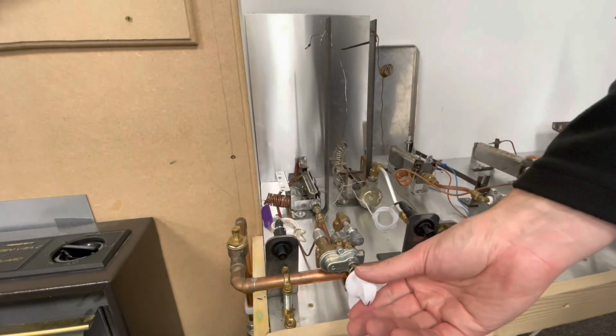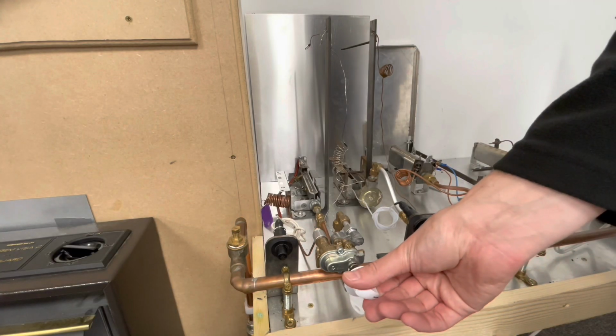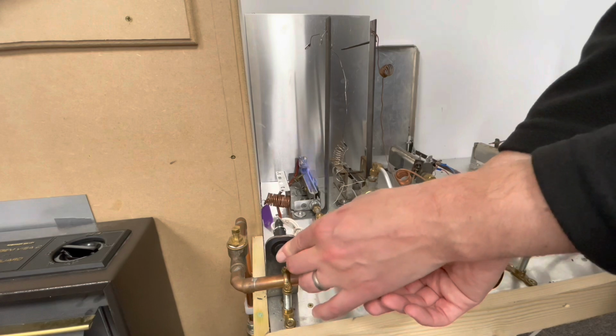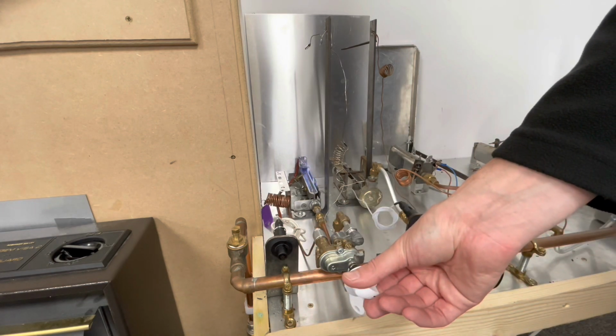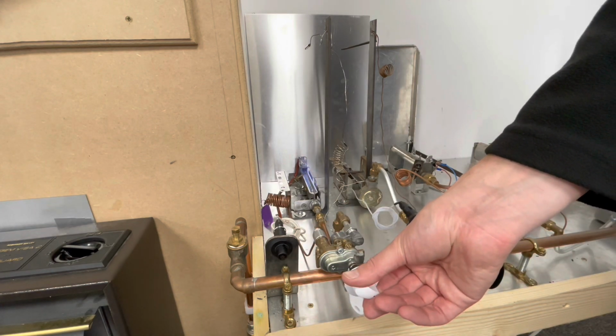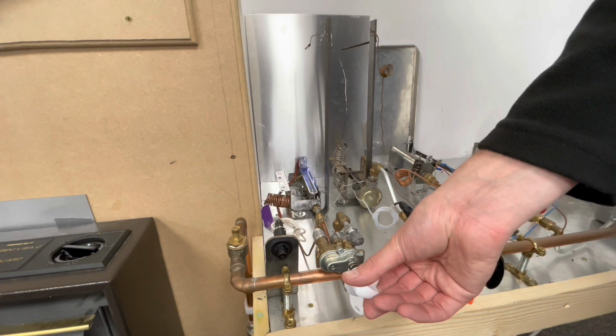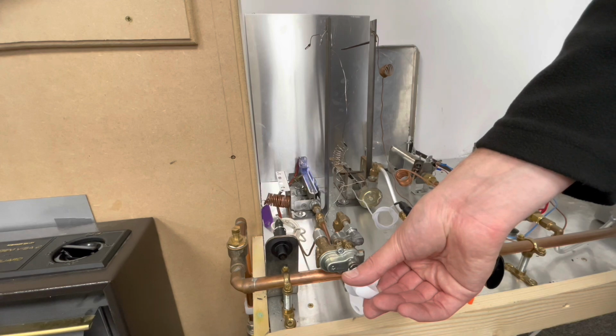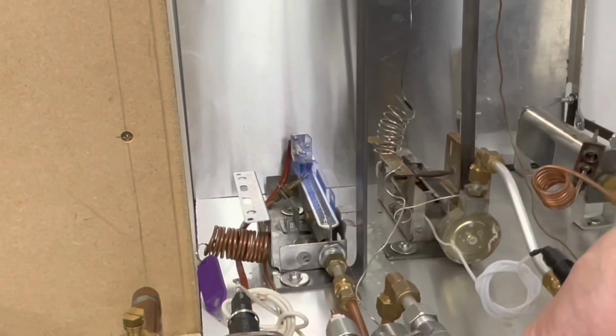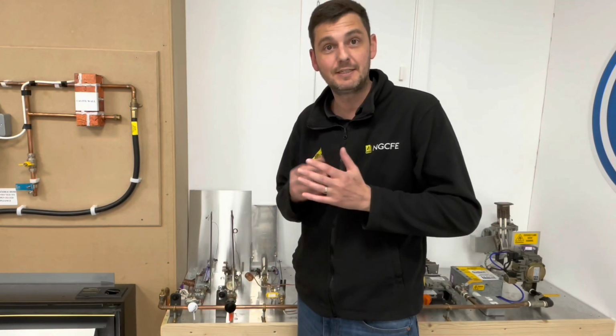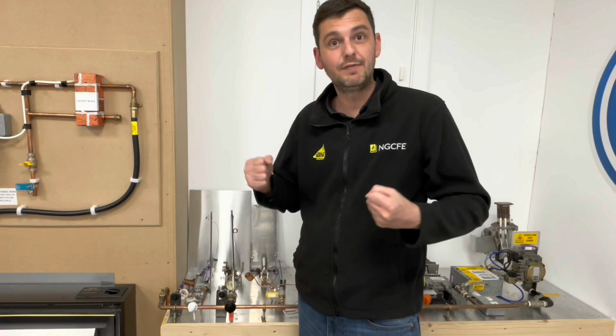So now we're going to look at how, from start to finish, the operation of this control works. So the first thing we're going to do is turn the gas on, and we're going to ignite it using the piezo igniter. We can see now that the flame is present and it's on full rate. Once the thermocouple is now getting hot, the dissimilar metals are now creating an electric current, and I can now remove my hand from there, and because the magnet's energized, it's holding the valve open.